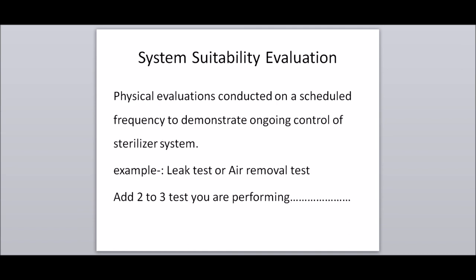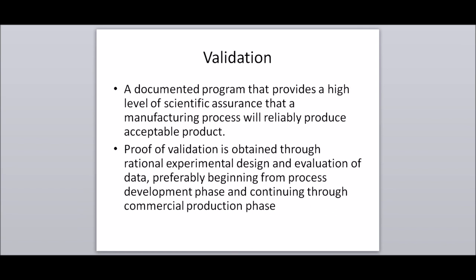System suitability evaluation: a physical evaluation conducted on a scheduled frequency to demonstrate ongoing control of a sterilizer system, for example, a leak test or air removal test. Validation: a documented program that provides a high level of scientific assurance that a manufacturing process will reliably produce acceptable product.